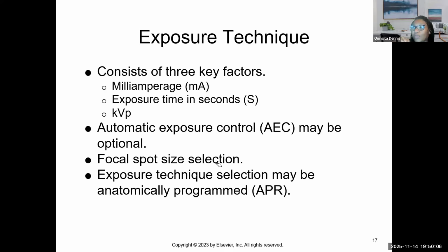All right. So with bone, since it's radiopaque, it's harder to penetrate. So the machine itself is trying to say, okay, I'm going to stop when enough radiation is reached. But instead of it being air-filled lungs, it's trying to detect for the center cell, which the spine is over. So that exposure is going to stay on longer than it should. Back in the day, it would have resulted in an overexposure. I mean, it is an overexposure for the patient, but it would have been a darker image. With the newer technology, sometimes it's an overexposure for the patient, but the image may still look good.